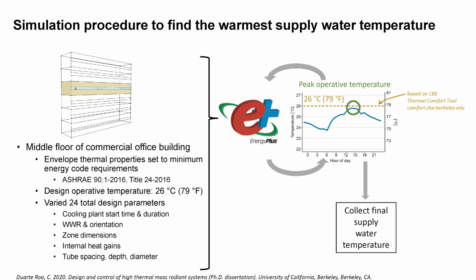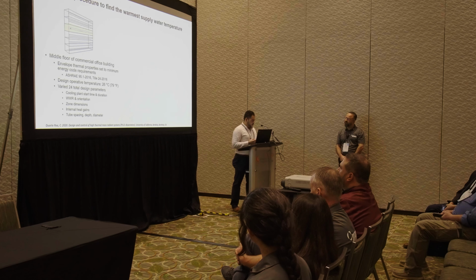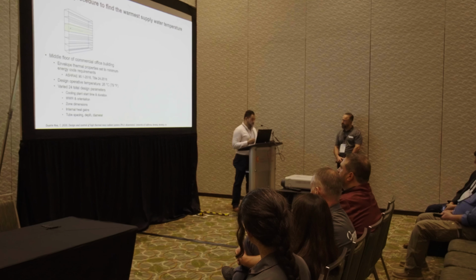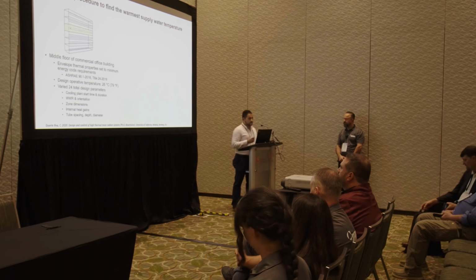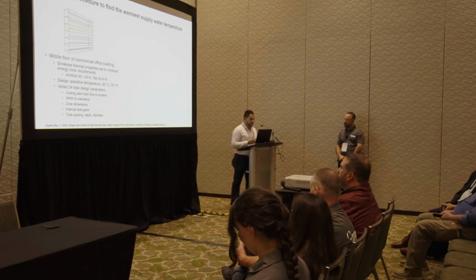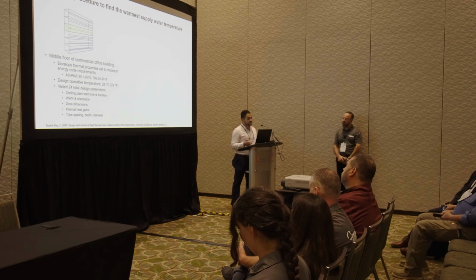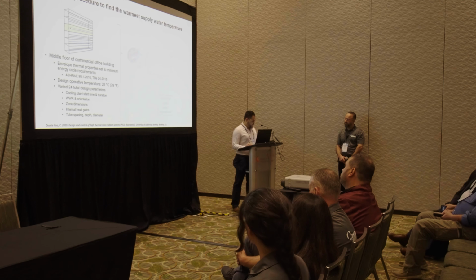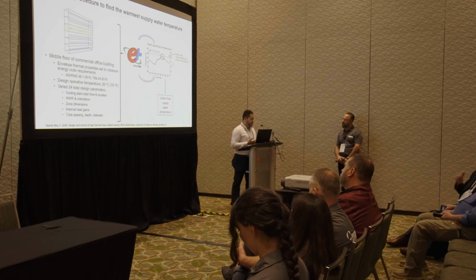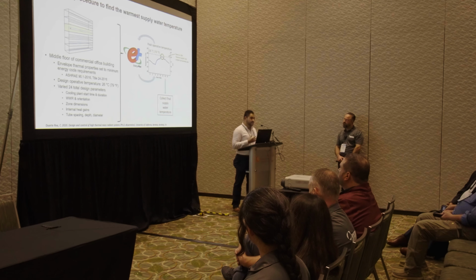And to figure out what is the actual potential of using water side economizing in high thermal mass, we developed a simulation study where we estimated the actual supply chilled water temperatures needed for the radiant systems in order to provide a thermally comfortable environment for the space. So we developed a model that represented a commercial office building with various designs and radiant system parameters. So we set the building envelope to the minimum energy code required by the city's code, and then we varied other 24 total parameters that included window to wall ratio, the orientation, zone dimensions, internal heat gains, radiant system parameters like tube spacing, depth, the pipe diameter. But when it was all said and done, we created over 360,000 models to simulate in EnergyPlus on the city's cooling design day.